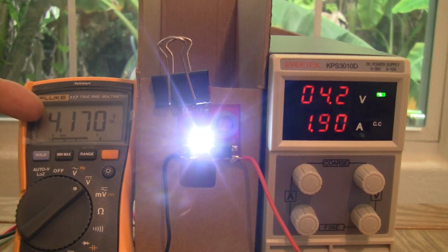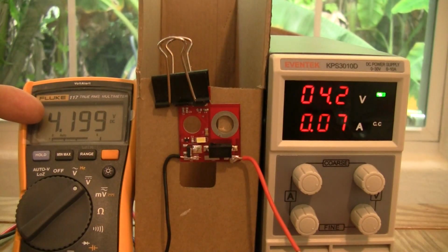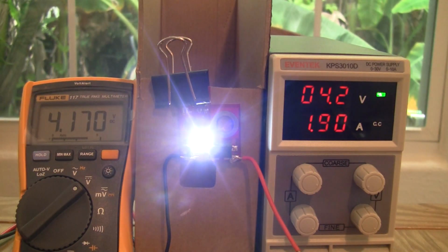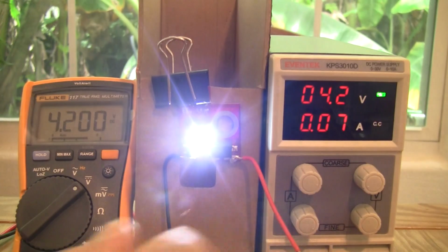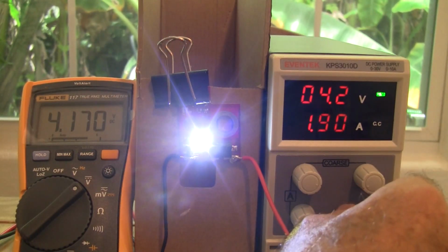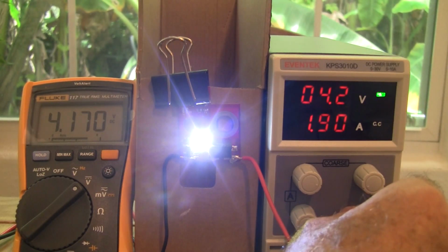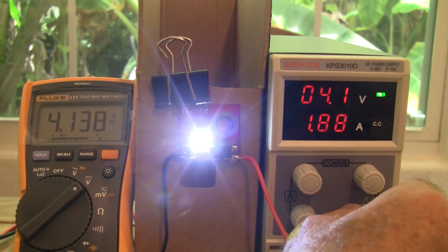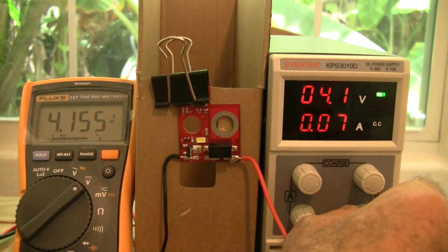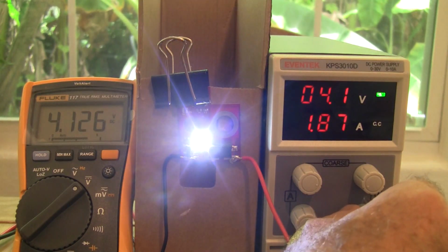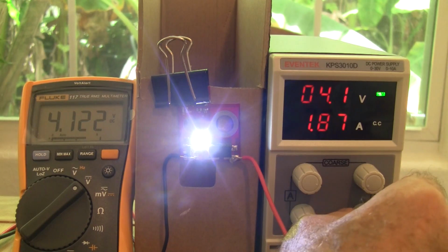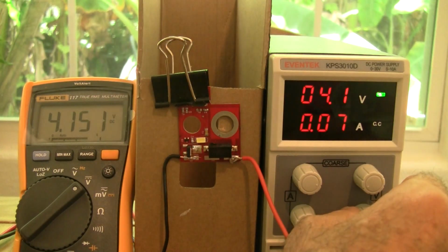So the voltage on this Fluke meter is 4.19 when it's not burning and 4.17 when it is. See, there's 4.199. Okay, let's slowly bring it down to where it shuts off. And now it's 4.155, still a bit too high. I'm not looking at this, I'm waiting for the interval to judge the voltage. 4.151, and it's staying off.